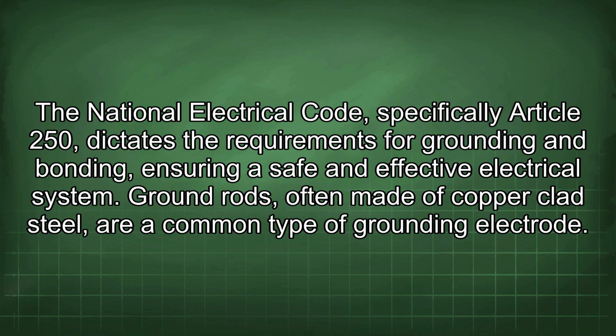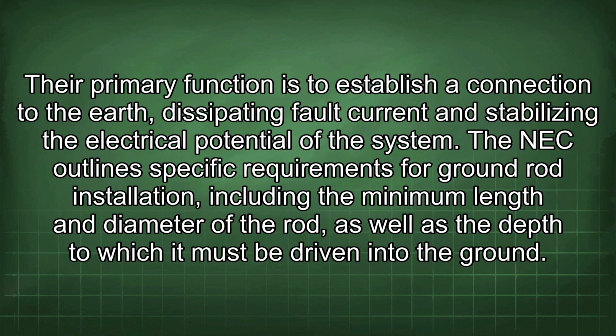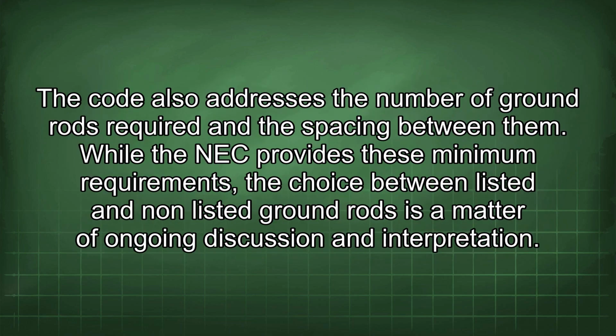system. Ground rods, often made of copper-clad steel, are a common type of grounding electrode. Their primary function is to establish a connection to the earth, dissipating fault current and stabilizing the electrical potential of the system. The NEC outlines specific requirements for ground rod installation, including the minimum length and diameter of the rod, as well as the depth to which it must be driven into the ground. The code also addresses the number of ground rods required and the spacing between them.